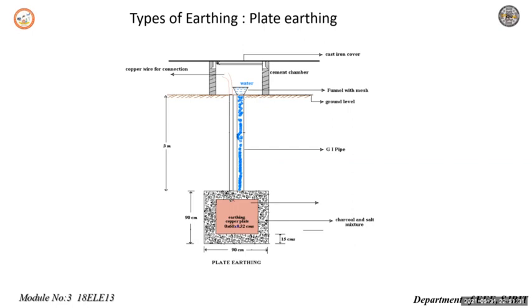When the insulation of the machine is perfect, the insulation resistance is of the order of a few megaohms and practically can be considered as infinity. So in normal operating conditions, no current passes through the body of the person and hence there is no danger of shock. But when the insulation becomes weak or defective, or if one of the windings touches the frame directly due to some fault, then the insulation resistance becomes almost zero. Now the resistance of the body and earth are not very high, and hence the current increases to such a high value that the person receives a fatal shock. Such a current is called leakage current, and it is very dangerous. Hence, when the machine is not earthed, there is always a danger of shock under certain fault conditions.